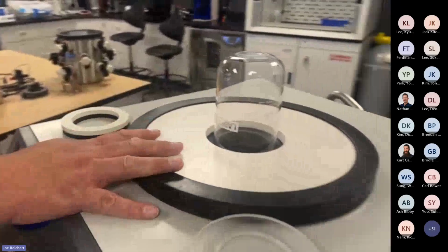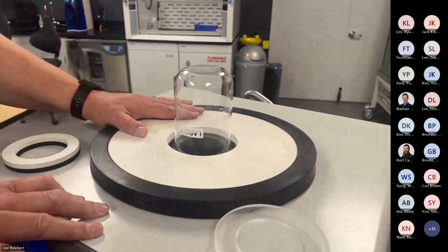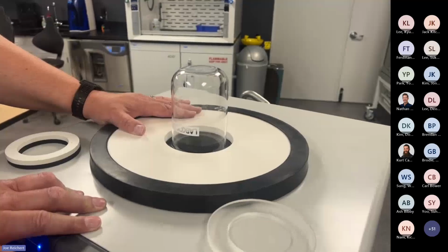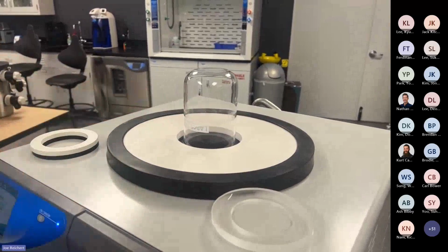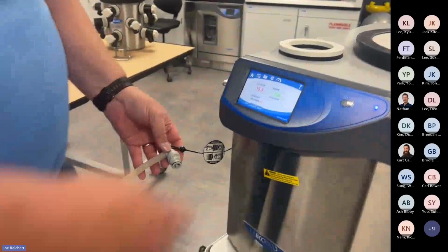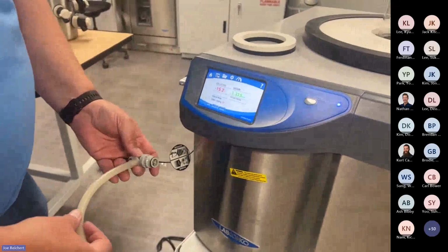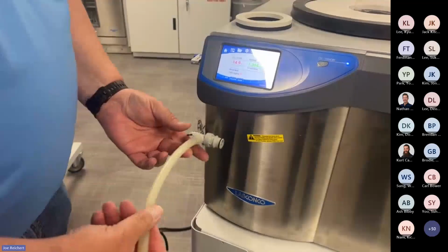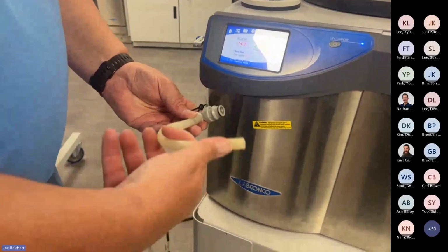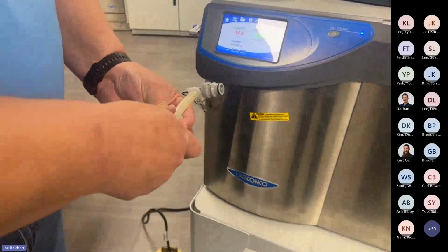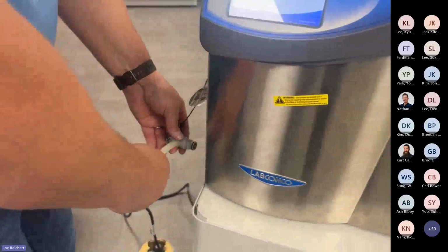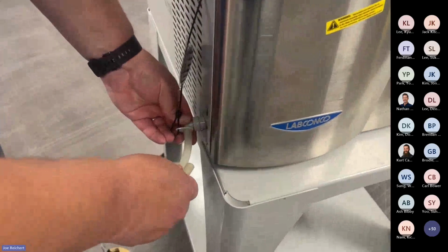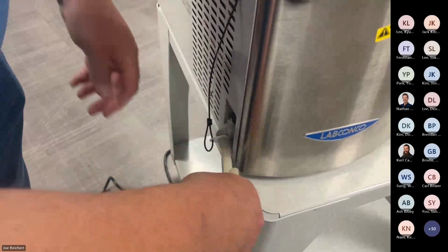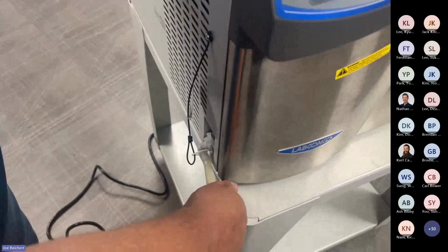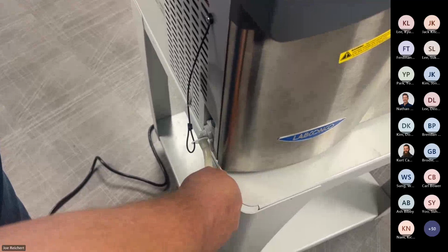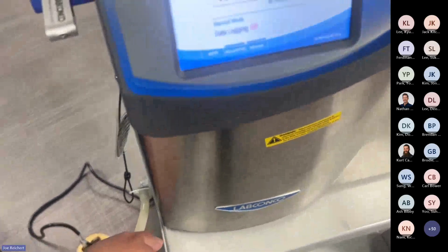But if you don't get a vacuum like this, then you could still possibly have leaks inside the chamber, or it could be from your drain port itself. Now, obviously, I'm getting a vacuum here, but if I did not have a vacuum, I can take my silicone hose that comes with it, and all you do is just bend it over and kink it like this. You can just hold it by hand and then insert it into your drain port. And I shouldn't lose any vacuum except for the little bit that was in that hose. And then it's going to come back down.